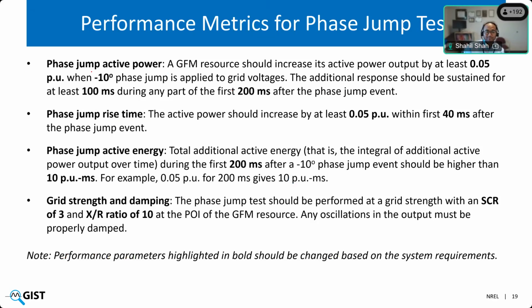So the first performance metric is phase jump active power. A grid forming resource should increase its active power output by at least 5% or 0.05 per unit when a negative 10° phase jump is applied to its grid voltages.